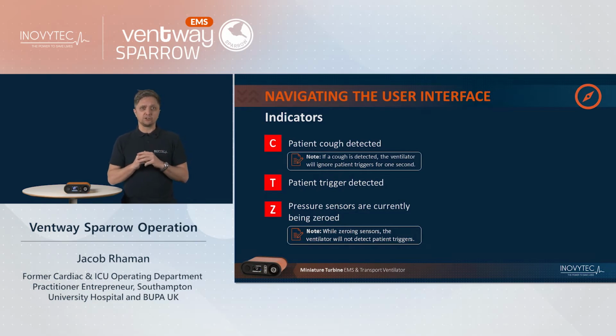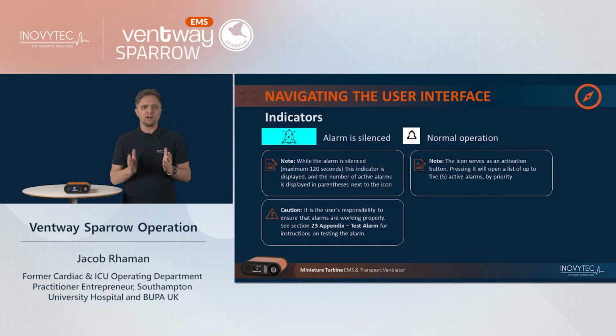T, patient trigger detected. When the patient takes a breath, a red T is shown. Z, pressure sensors are currently being zeroed, shown as a red Z. While zeroing sensors, the ventilator will not detect a patient. When using the alarm, the bell with a cross indicates the alarm is silenced. While the alarm is silenced for a maximum of 120 seconds, this indicator is displayed, and the number of active alarms is displayed in parentheses next to the icon.